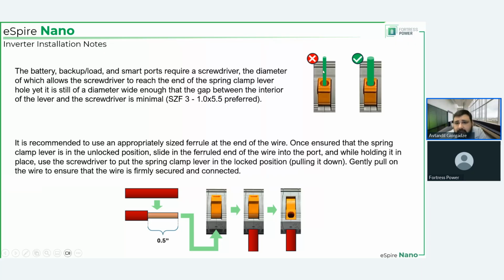If that is not the case, if a very narrow screwdriver is used, once you start applying downward force, which will create torque, you might crack this bottom portion of this inlet, and that will be a problem. So the diameter should be as close as possible, and the inlet itself does not have a cylindrical shape. It has more of a cone shape, which ends in a line. That's why the flathead screwdriver needs to go in to accommodate that shape, so that the torque is applied fully onto the entire clamp and not only on a portion of it. Because if it's applied only on one portion, that portion is going to crack open.